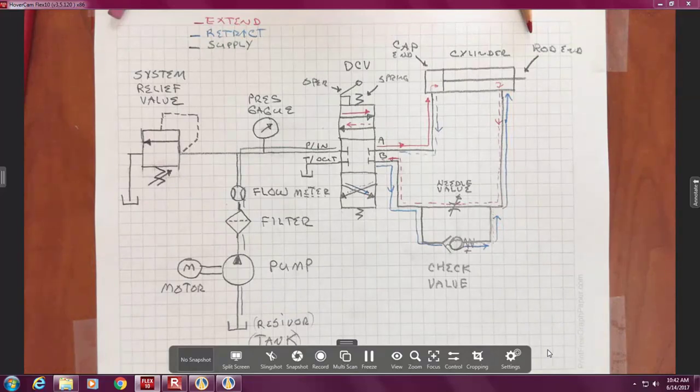It means I can withstand 5,000 PSI. So I think these pumps in our hydraulics are either 3,500 or 5,000, that's the spec. It's saying I can withstand 3,500 trying to come back through me. But with a one horse motor, I can only produce 600 PSI. It's a function of lift, right? My bicep determines what I can lift. It's not a math equation.